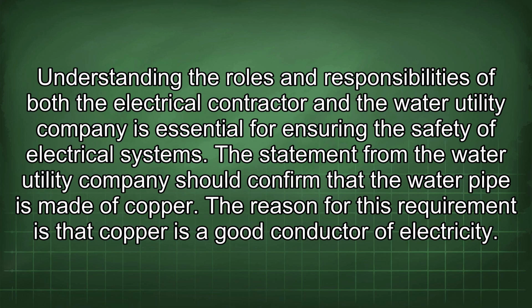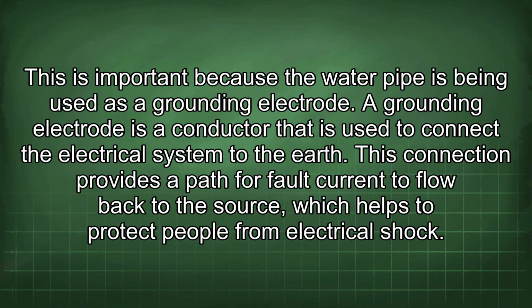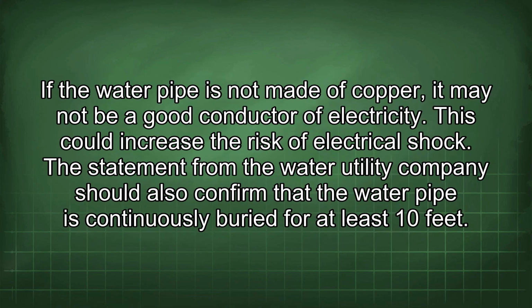The statement from the water utility company should confirm that the water pipe is made of copper. The reason for this requirement is that copper is a good conductor of electricity. This is important because the water pipe is being used as a grounding electrode. A grounding electrode is a conductor that is used to connect the electrical system to the earth. This connection provides a path for fault current to flow back to the source, which helps to protect people from electrical shock. If the water pipe is not made of copper, it may not be a good conductor of electricity. This could increase the risk of electrical shock.